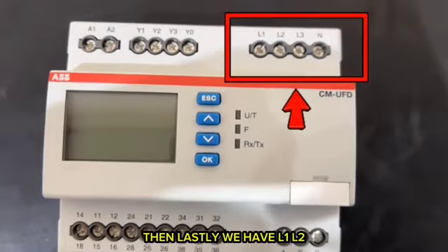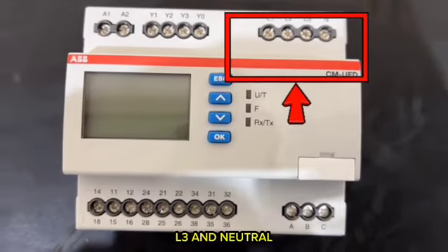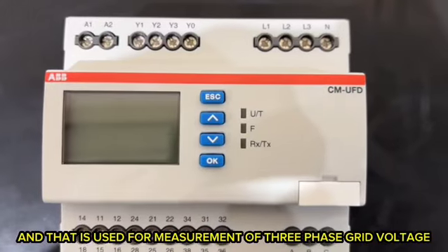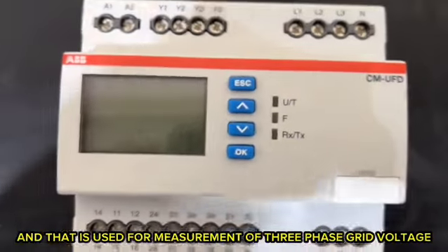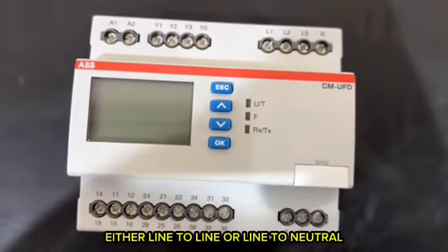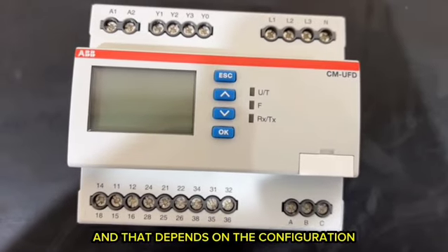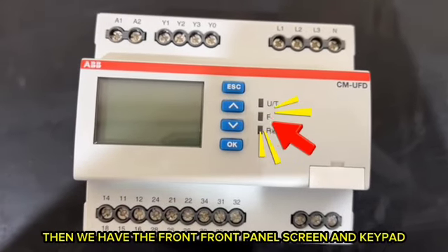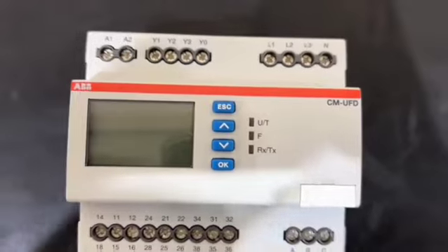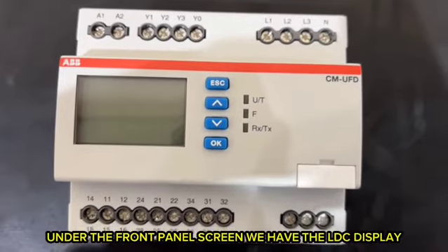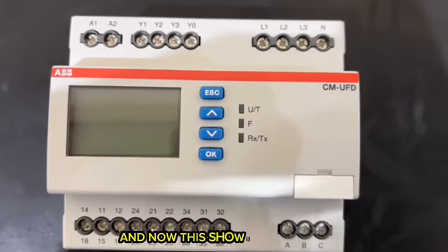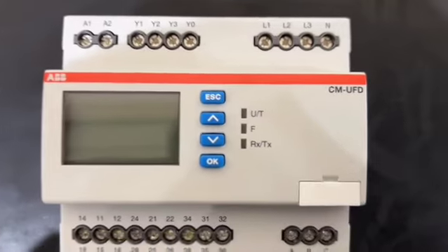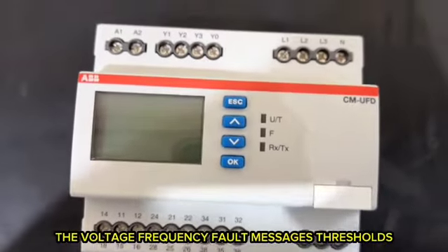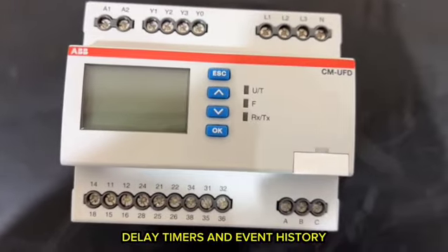Then lastly we have L1, L2, L3 and neutral, and that is used for measurement of 3-phase grid voltage, either line to line or line to neutral, depending on the configuration. Then we have the front panel screen and keypad. Under the front panel screen, we have the LCD display, and this shows the grid values, the voltage, frequency, fault messages, thresholds, delay timers and event history.